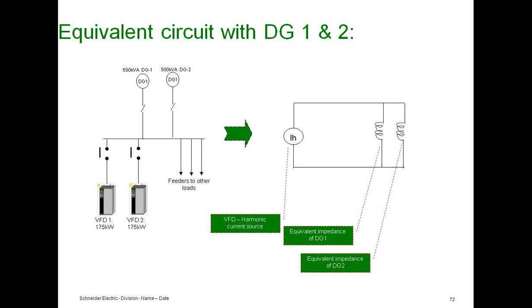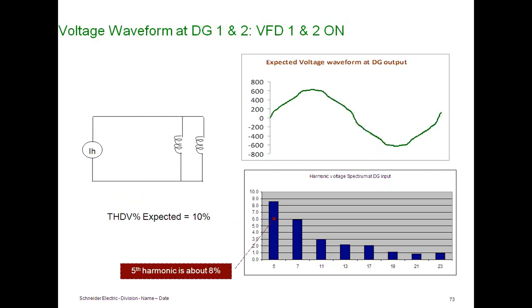With the generator on, and feeding the VSD, theoretically the harmonic expected was 10% on the voltage side, out of which fifth harmonic was dominant, close to 8.5%. So this was causing a big issue, and it was creating negative torque on the generator winding, and it's tripping with negative sequence delay action.